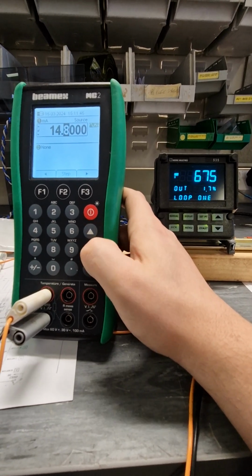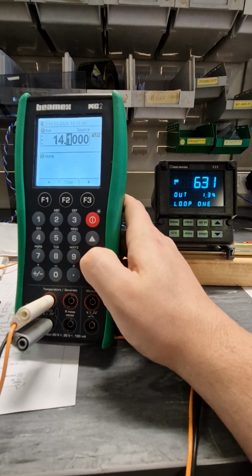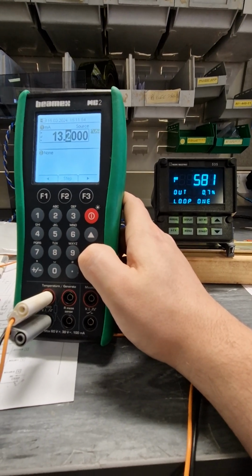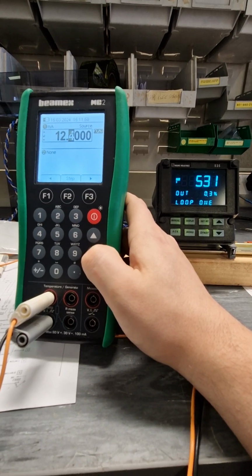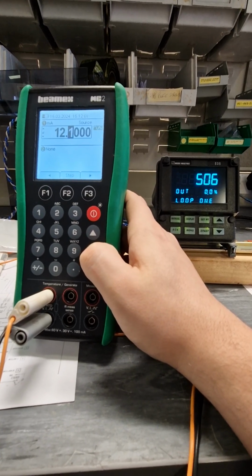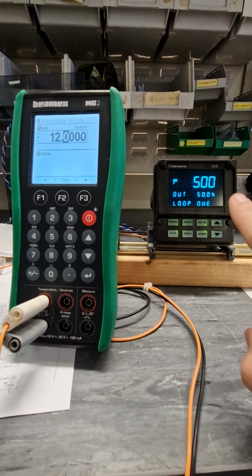And that's kind of proving the point that it is possible to go to pretty much 0 on the output based on deviation from set point. And then going back below, it's immediately automatically gone back into the proportional control.